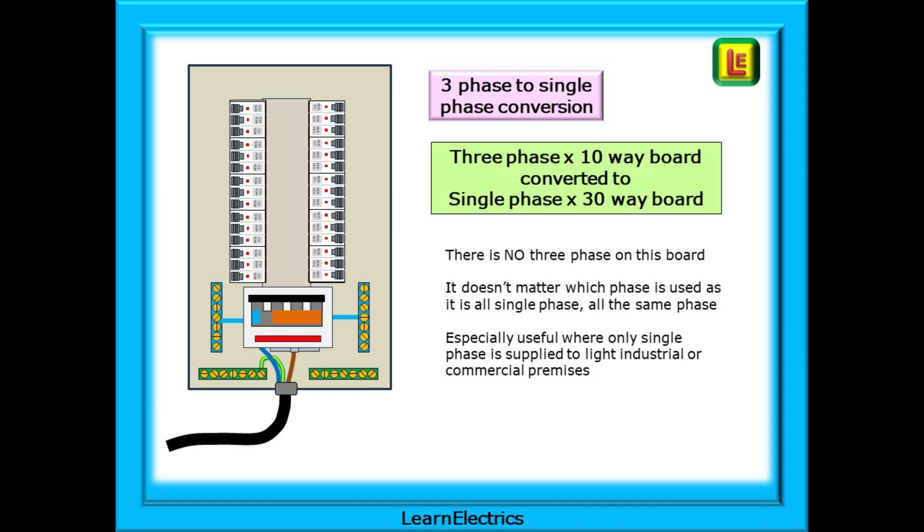Our 10-way three-phase distribution board is now a 30-way single-phase board. Useful if you only have single-phase and you need lots of individual circuits. Install the appropriate single-phase circuit breakers, RCBOs, SPDs, and so on, and all should be good. This could also be a sub-board, a single-phase supply from a three-phase board to an area in the unit where only single-phase is required. Of course, domestic-type consumer units could be used and they do come in double-height units and may be more appropriate for what the customer wants.